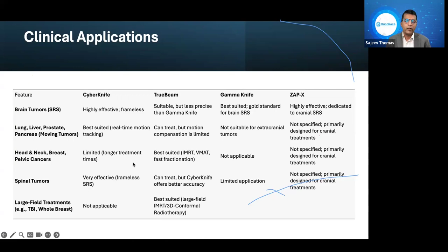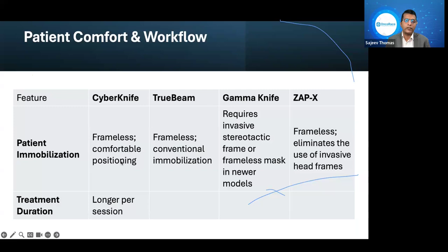So if you look at the patient comfort and workflow, patient immobilization, frameless, comfortable positioning with the CyberKnife. TrueBeam also frameless, conventional, and immobilization. Multiple options available with the TrueBeam now. Gamma Knife requires an invasive stereotactic frame, or a frameless mask in newer models. ZAP-X is frameless, eliminates the use of invasive head frames. So the treatment time is longer sessions.